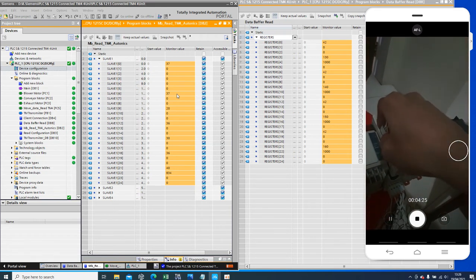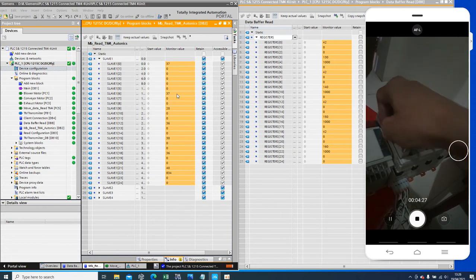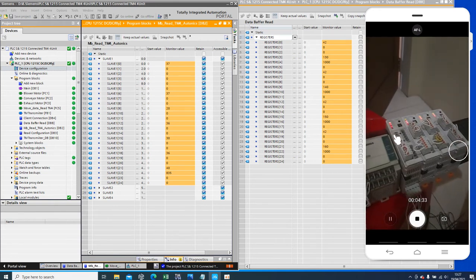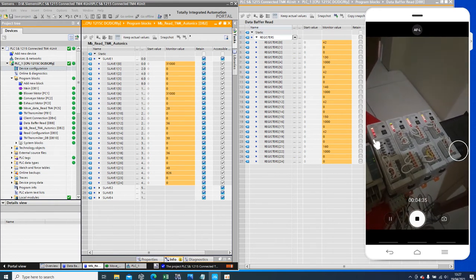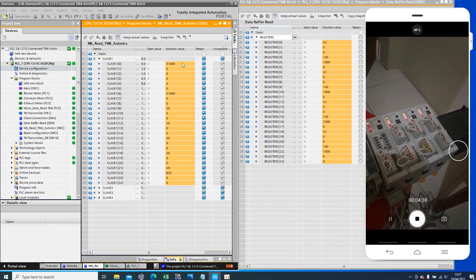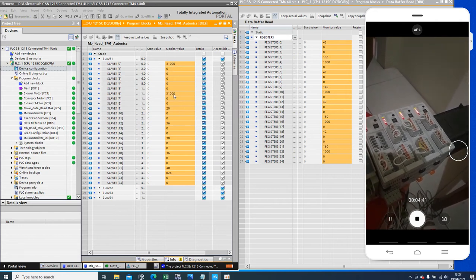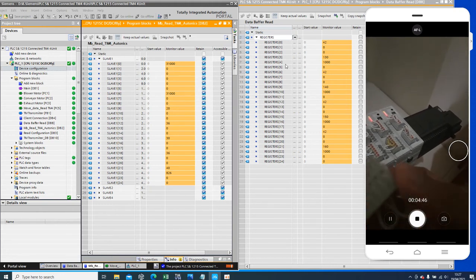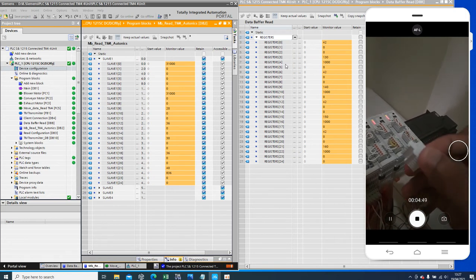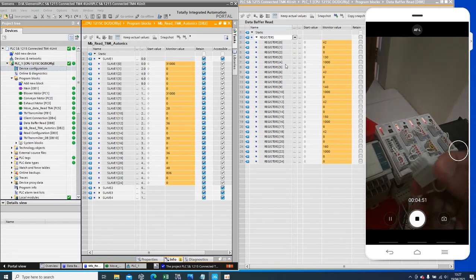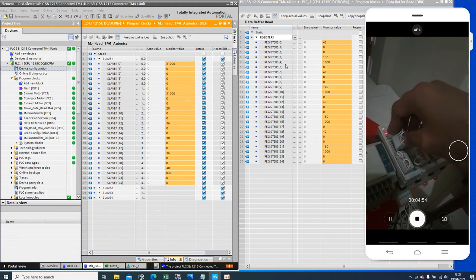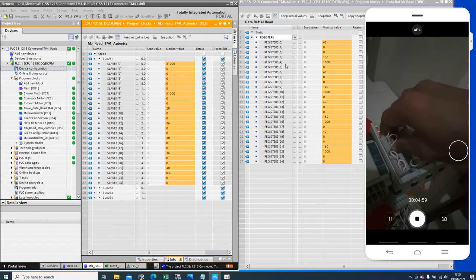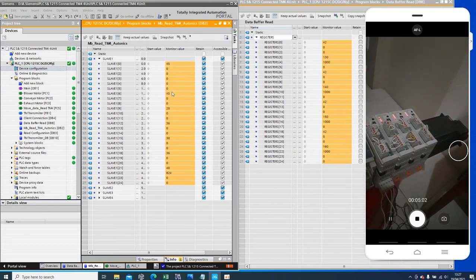Let me show you — I will take this connector. I already took the connector. It doesn't have a connector anymore, so the value means it doesn't have a sensor. So if I take this out, I can install it again or connect it to the module again, so the actual temperature will be back — you see, 45 and 45.